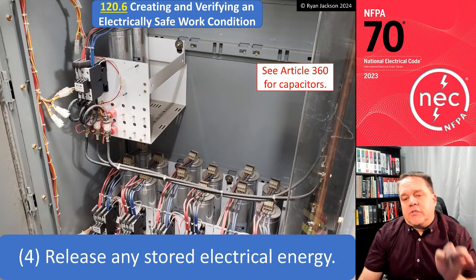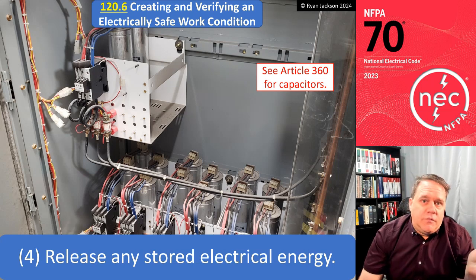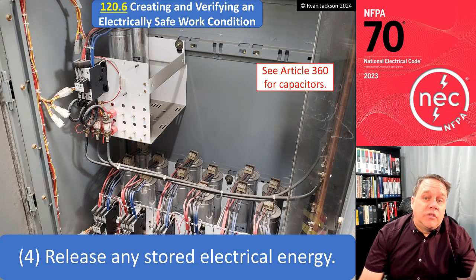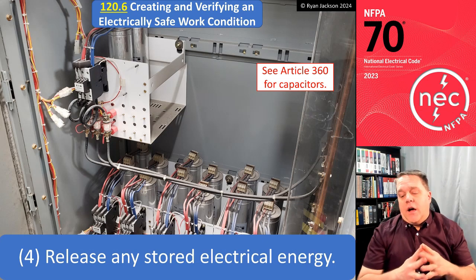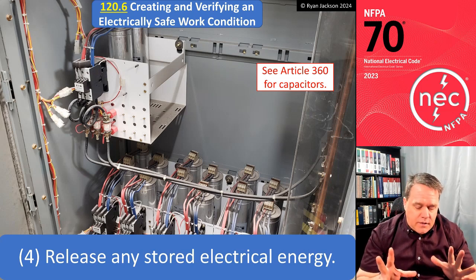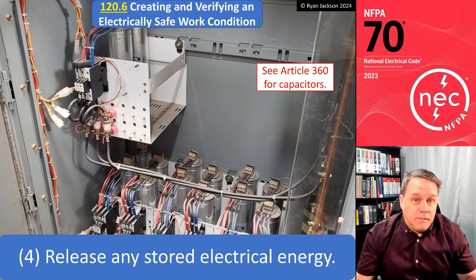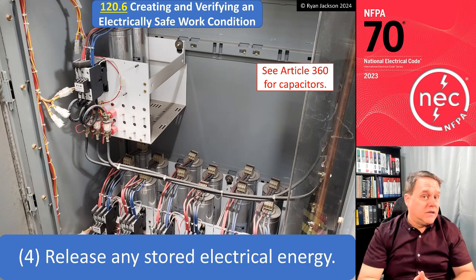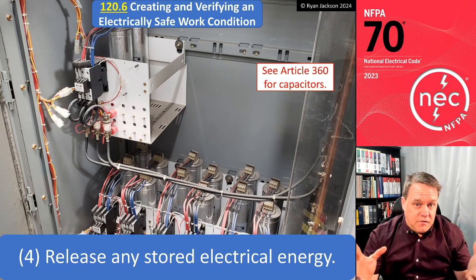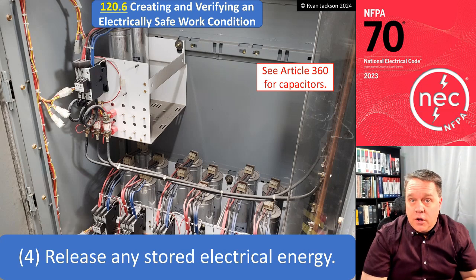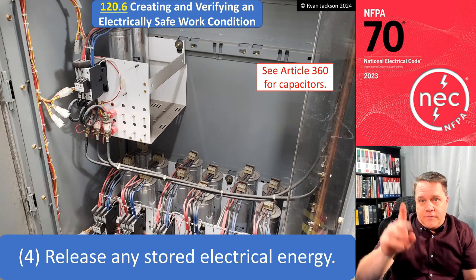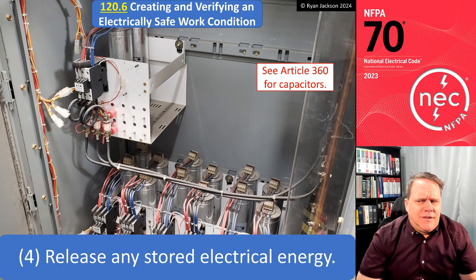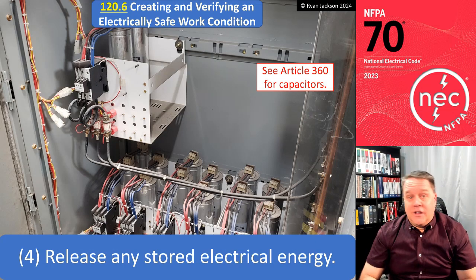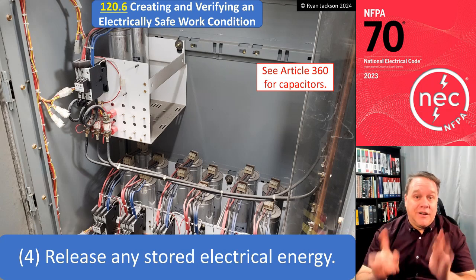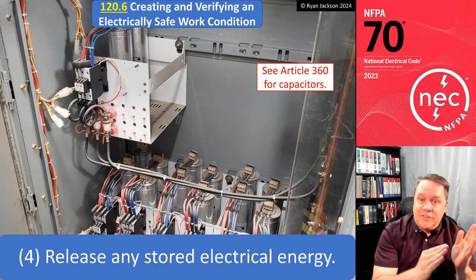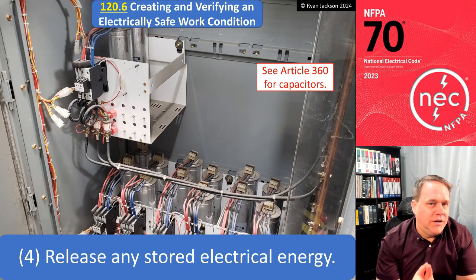Item 4, release any stored electrical energy. A lot of times this is having to do with capacitors, and a lot of times with capacitors now, because more and more equipment has capacitors in it, a lot of times if there's a bleed off resistor, the way you release any stored energy is to just wait. You shut it off and you just look at your watch and you wait. I saw a small residential solar PV inverter where the instructions say, do not open it until after shutting off and waiting 30 seconds. And it's like, how stupid is that? You shut it off and hang out, wait for 30 seconds? Not stupid at all, because there's still power in those capacitors. And those capacitors take a little bit of time to discharge, all right? So let's release any stored electrical energy.